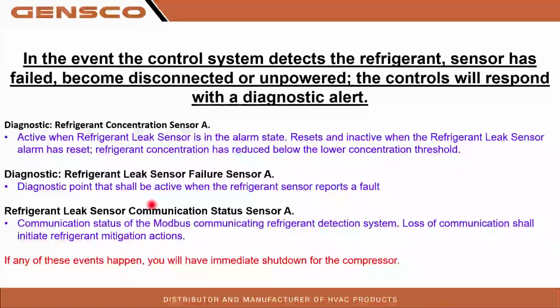And again, if it detects refrigerant or if the leak sensor has failed, maybe the frostat has failed and we have ice buildup and the ice has wrapped around the leak sensor and ruined it, right? So I don't know if we're going to have to replace these every 4 years or not, but it might be wise to keep a couple extra in stock on your commercial service rigs to change them out, even as preventative maintenance because it is a safety device.